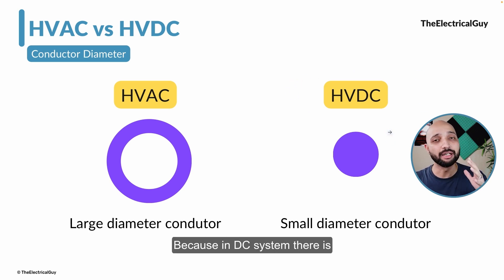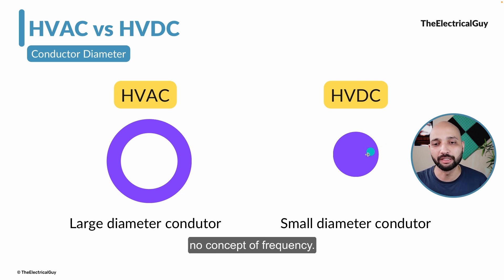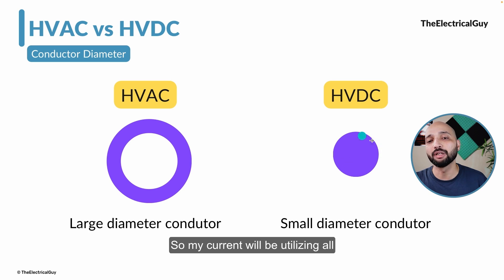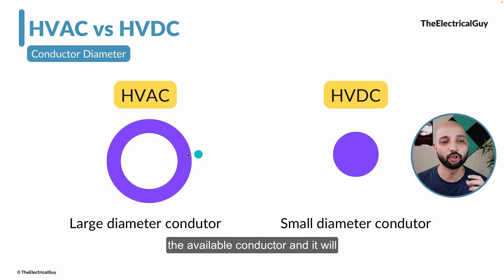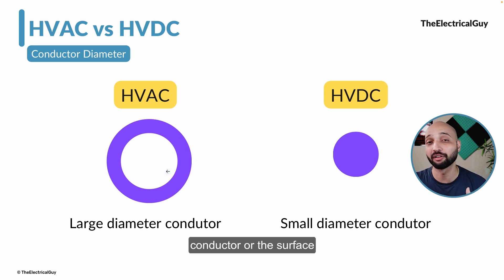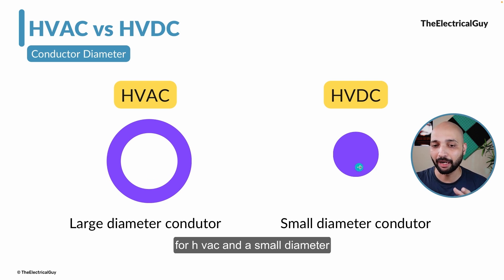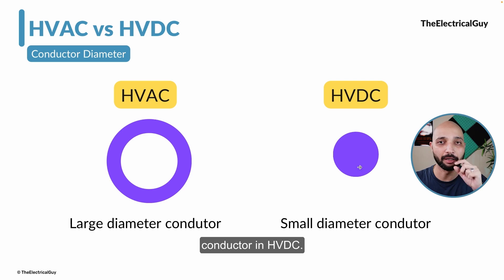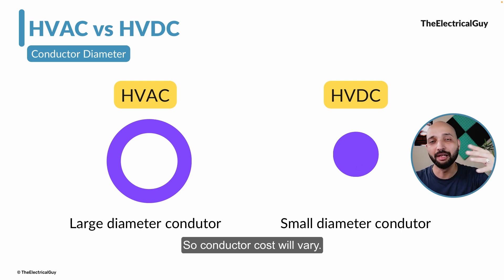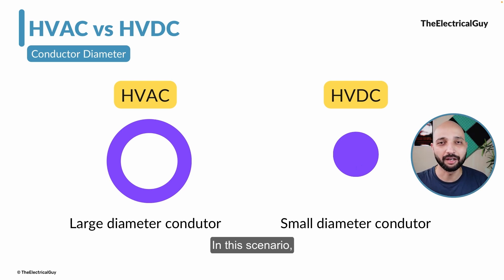In a DC system, there is no concept of frequency, so the current utilizes all the available conductor and does not concentrate on the surface. To transmit a similar amount of power, I will need a large diameter conductor for HVAC and a small diameter conductor for HVDC. So conductor cost will vary between the two systems.